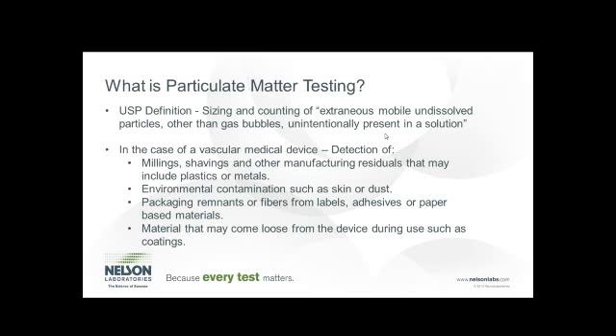The packaging of devices is usually significantly larger in surface area and more complex than that of a solution. Also, material that may come loose from the device during use is a big concern from regulatory — coatings such as hydrophilic coatings or drug coatings, mostly because this is a bit of a gray area. Sometimes these coatings are undissolved initially but may dissolve over time. However, because the undissolved nature of some of these coatings may cause issues in the patient for a short time, they're still of concern.